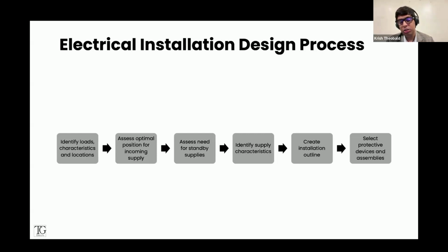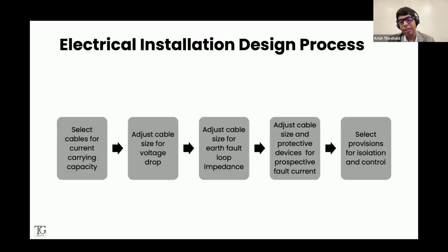Once we have all this information, we have to put it together and create an outline. This is done in two ways. Number one, we create a schematic starting with our source. I'll show you some examples as well. Going to your main distribution board, sub-distribution boards, loads, etc. Cables that you want to put in, so on and so forth. Where do you want to run the cables? This is generally done on the floor plan. Once you've decided what we want where, we need to now select our protective devices and assemblies. So this could be your circuit breakers, fuses, RCBOs, the actual panel boards, your distribution boards, so on and so forth. Then obviously it's a matter of selecting cables.